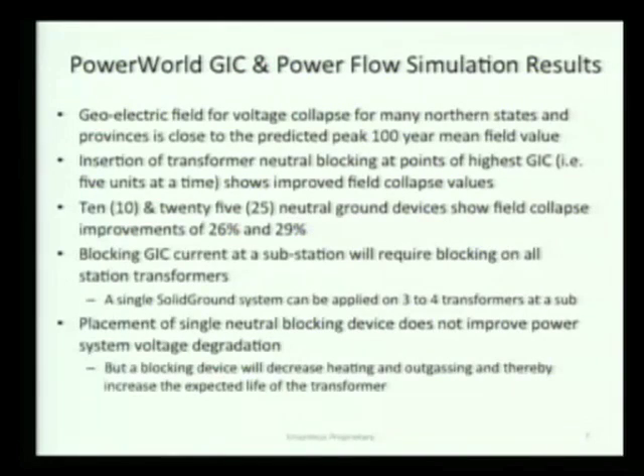What we're seeing here is collapse at 21 volts per kilometer, and we probably still have some errors in our modeling for the Wisconsin grid. So there's probably a range of, say, 15 to 25 volts per kilometer. But these ranges are just overlapping, and we're going to have to protect to the higher limit.